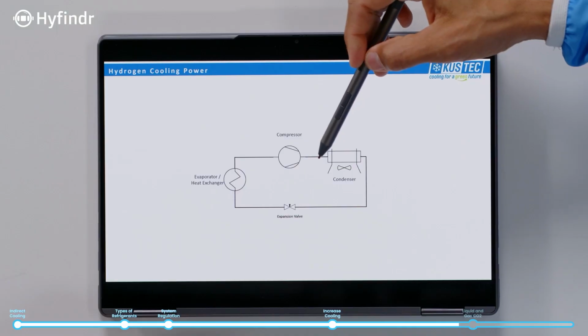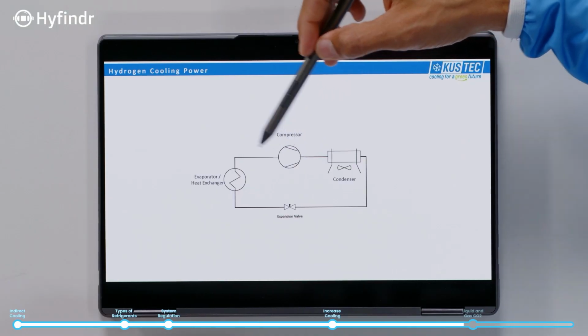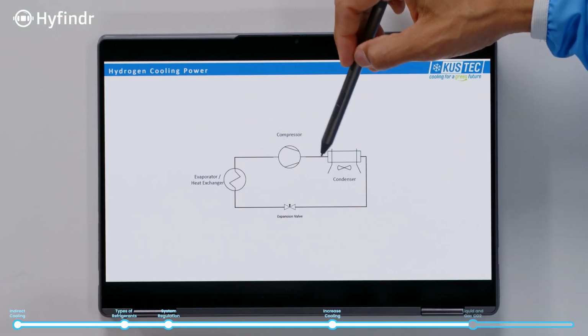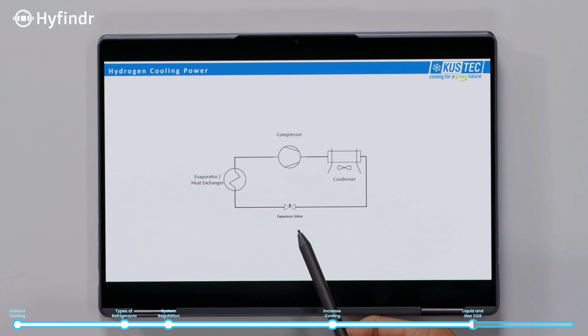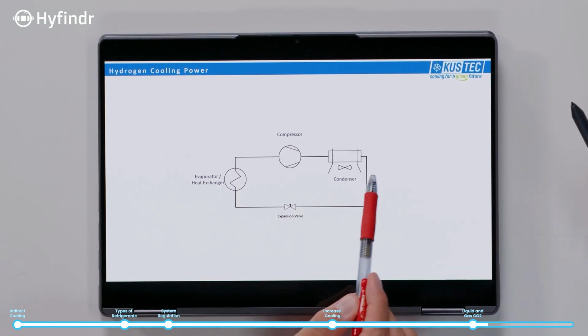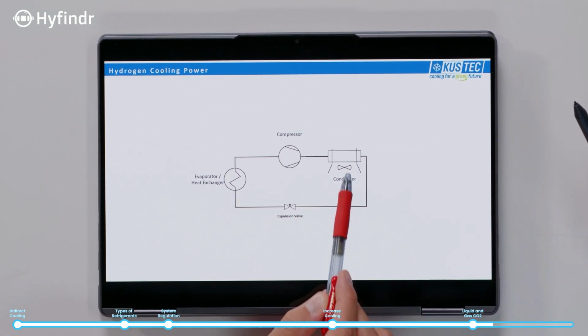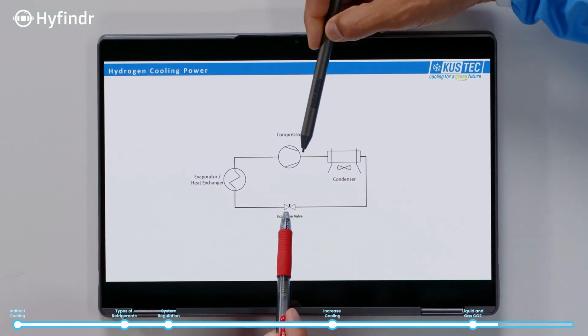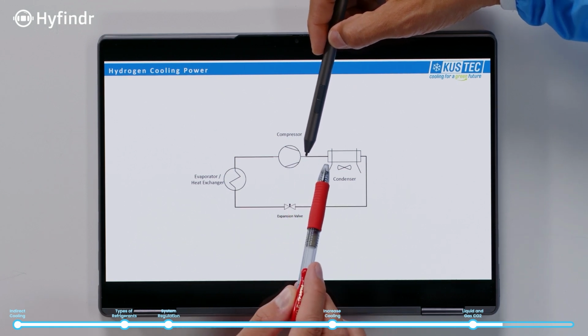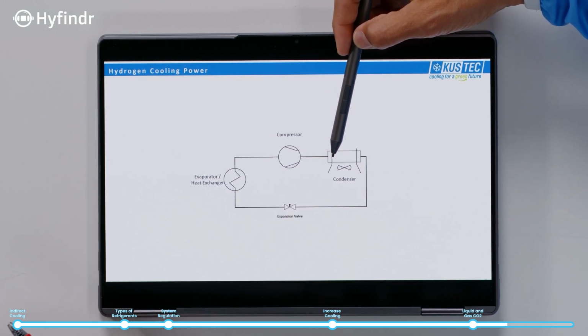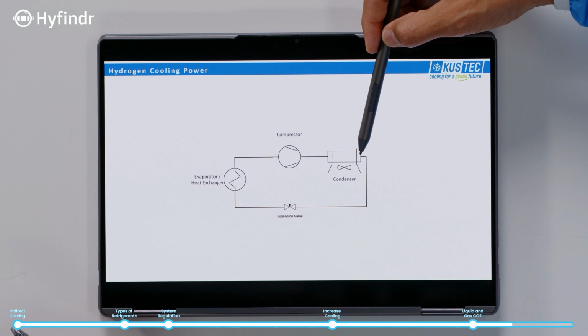Okay. Sorry for jumping a little bit, but you mentioned in the other one that you're using brine, and in this cycle you would use CO2. Where would the CO2 be liquid and where would it be gaseous? Again, can you just help us? It's getting liquid after the condenser. So it comes out gaseous here at a high pressure, high temperature, and then gets liquefied in there.